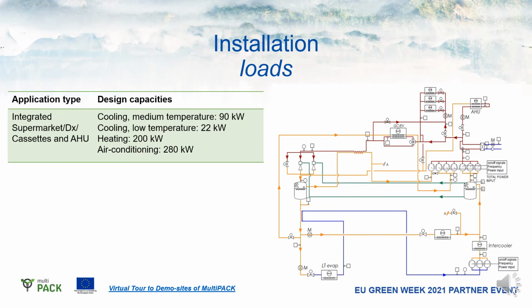Here in the system we can see that the unit has 3 low temperature compressors providing enough capacity for the freezing part, which is 22 kilowatt. The desuperheater rejects some of the heat. The medium temperature evaporators are rated to be around 90 kilowatt. The flow goes together in the low pressure receiver where the medium temperature compressors maintain the pressure.